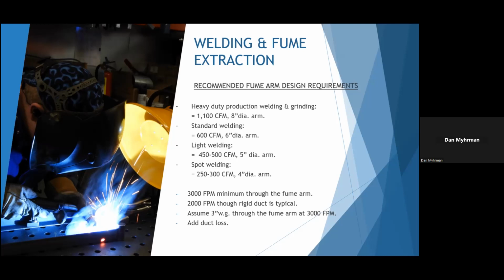As far as static pressure, these fume arms are always reaching various locations throughout the booths or whatever you're welding on, so the static pressure is never constant. A good starting point is about 3 inches of static, and that's assuming about 3,000 feet per minute through the arm. You're going to have to add your duct loss to that.